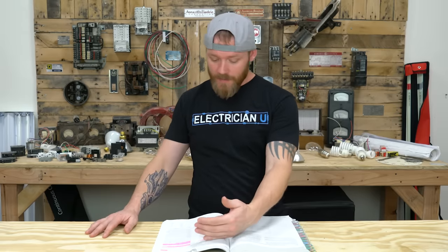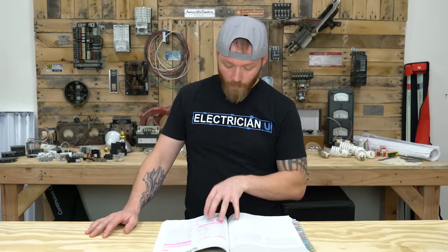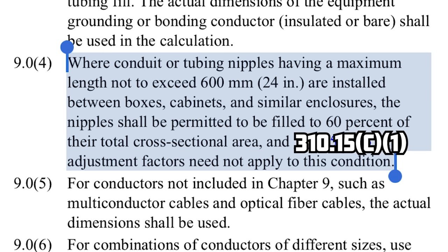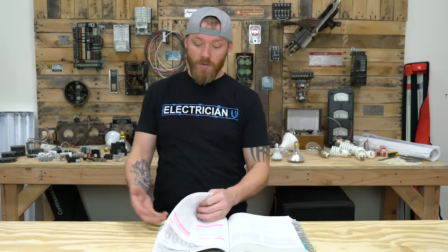Nipples allow you to go up to 60% area for your conduit fill, and you don't have to derate them. Looking at chapter 9, note 4 says: where conduit and tubing nipples have a maximum length not exceeding 24 inches and are installed between boxes, cabinets, and similar enclosures, the nipples shall be permitted to be filled to 60% of their cross-sectional area, and 310.15C1 adjustment factors need not apply. So you can put more conductors in a nipple, and you don't have to add any deratings.